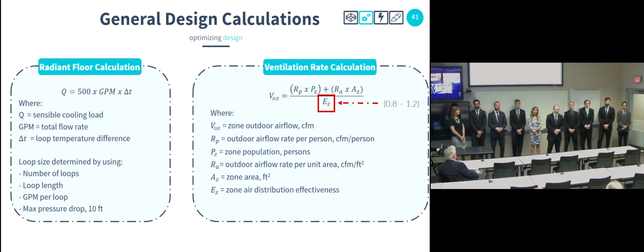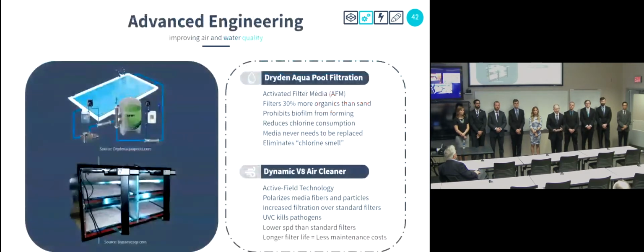On the left, we have some of our radiant floor calculation sizing. By solving for the GPM required to meet the sensible load of the space, we take that GPM divided by the number of loops in the space, and then based on the loop length and the industry standard of a max pressure drop of no more than 10 feet of head in a loop, we're able to size the PEX piping in those areas. For both the football field and the track and field, we sized our radiant floor piping at 3/4 inches.